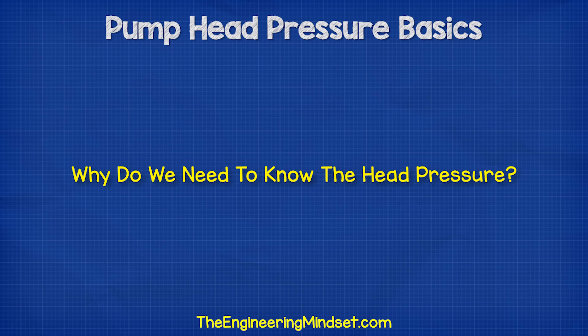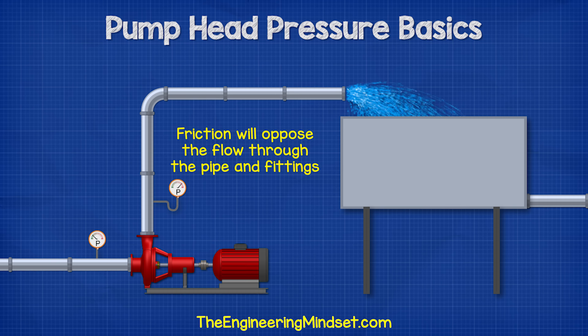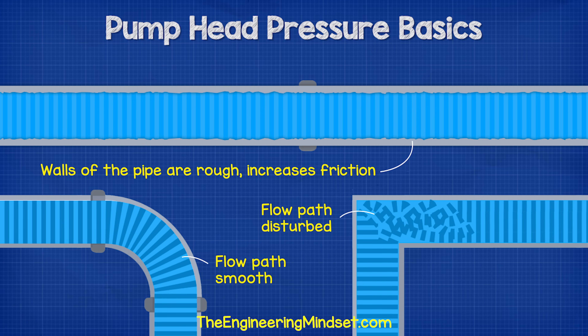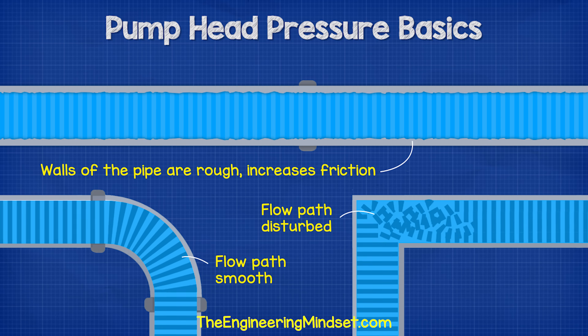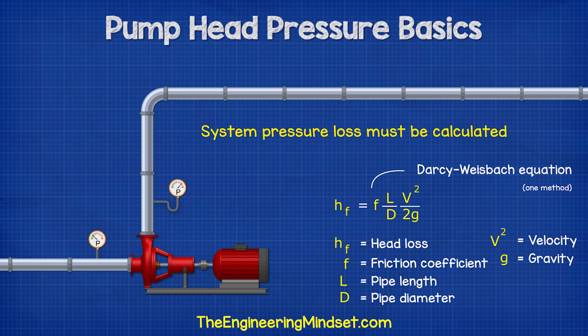Why do we need to know head pressure? Pumps are usually used to move liquid to a higher region, so we need to ensure the pump can reach this elevation. As we pump liquid through the pipes and fittings, friction will try to oppose the flow. This occurs from the walls of the pipe but also disturbances to the flow path, causing pressure losses which waste energy from the pump. The amount of friction depends on the liquid type as well as the materials and fittings used. Therefore, we must calculate how much friction or pressure loss our system will generate and ensure that the pump we select can overcome this.